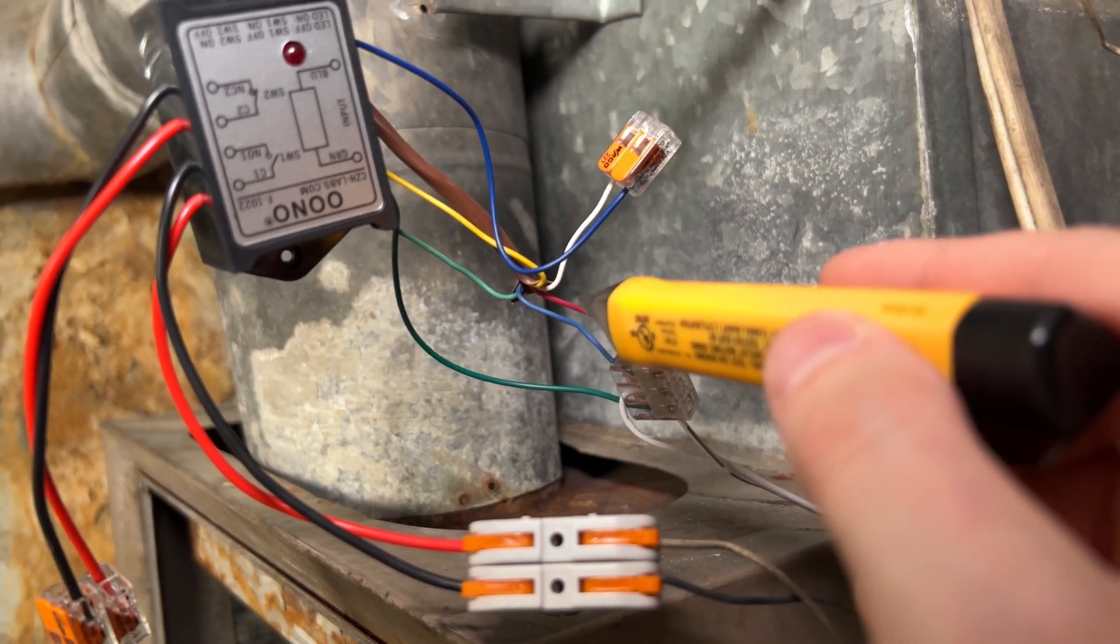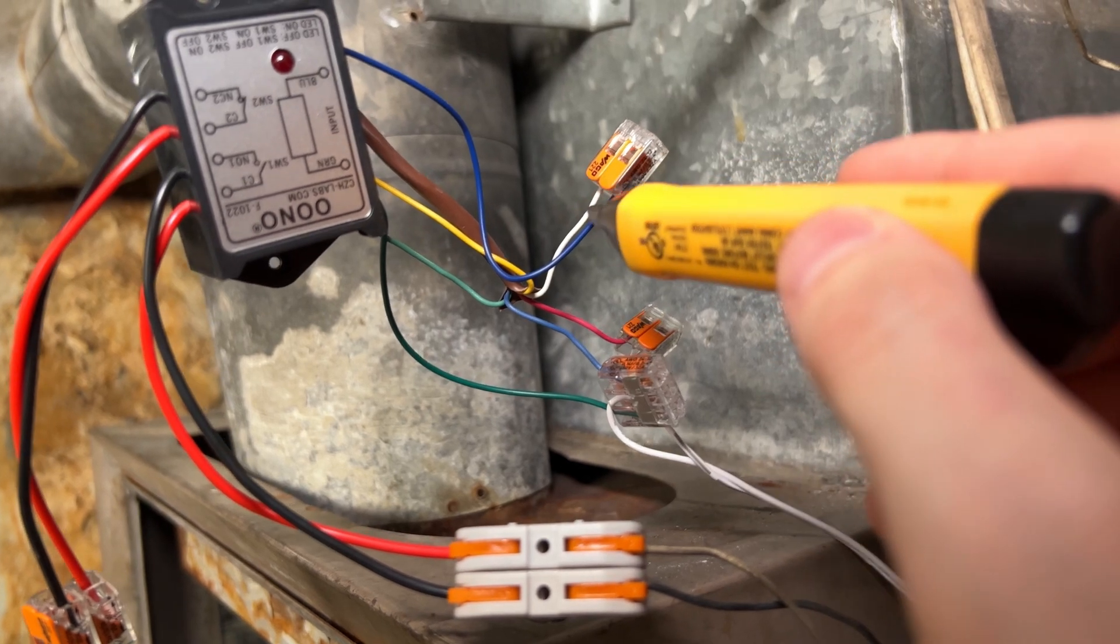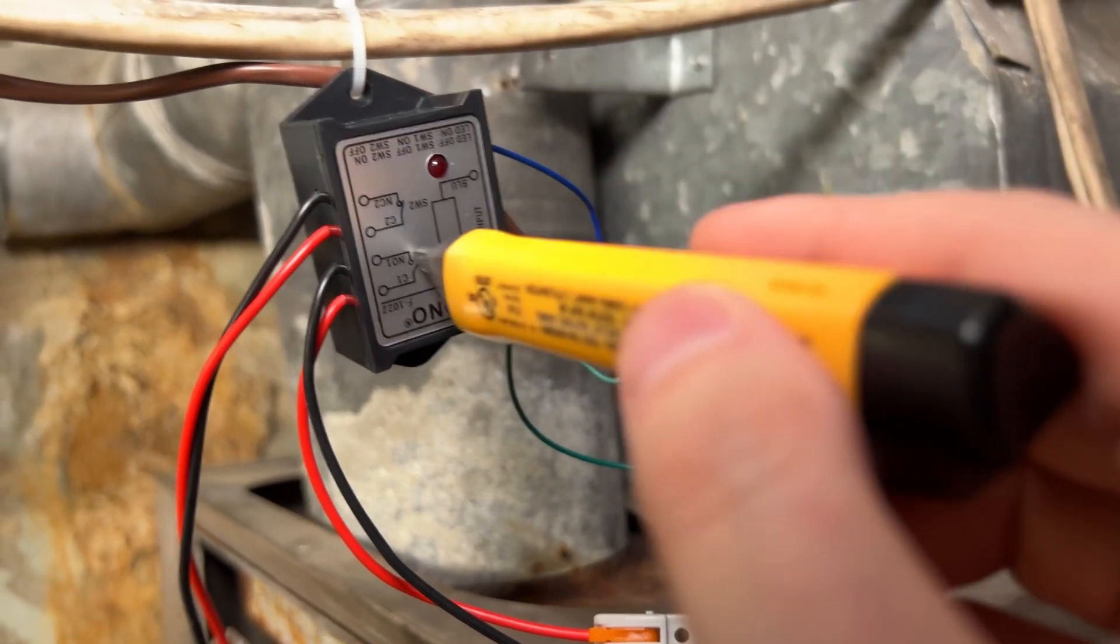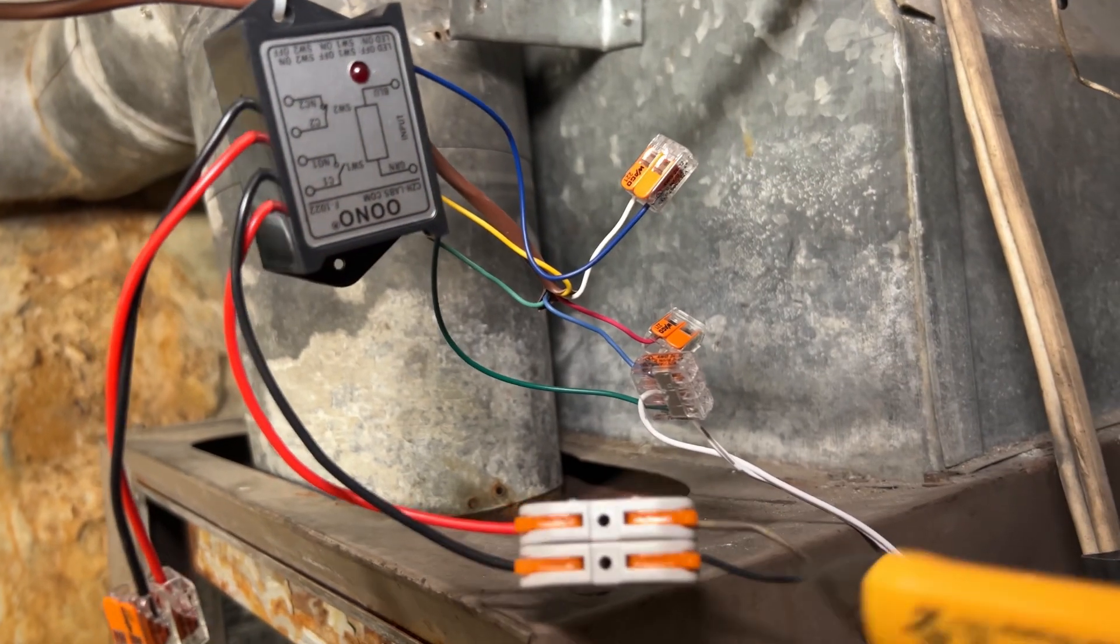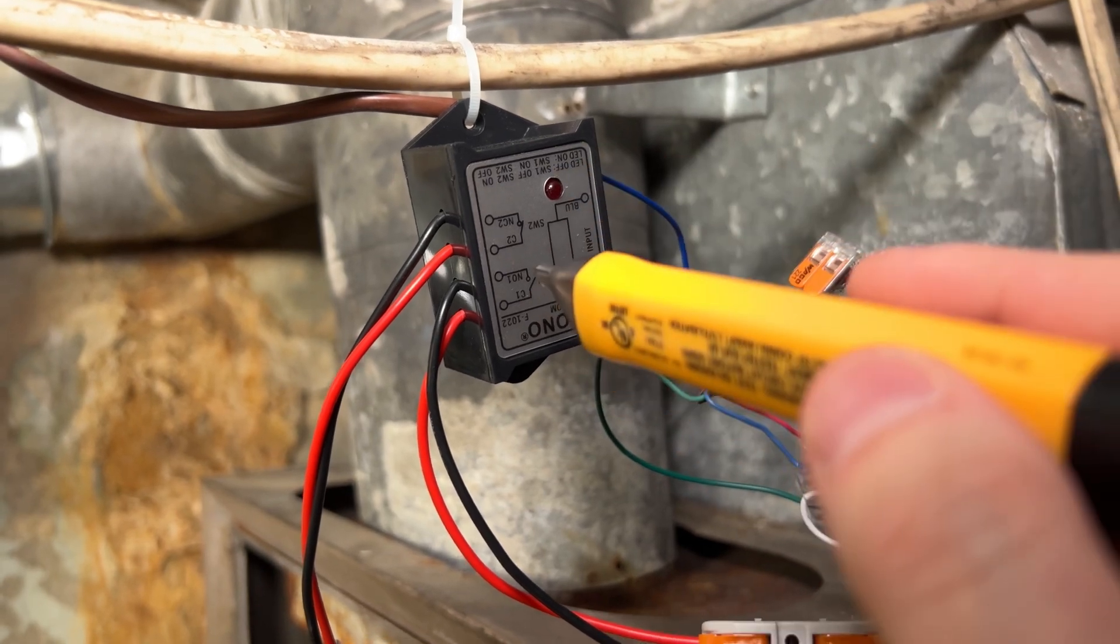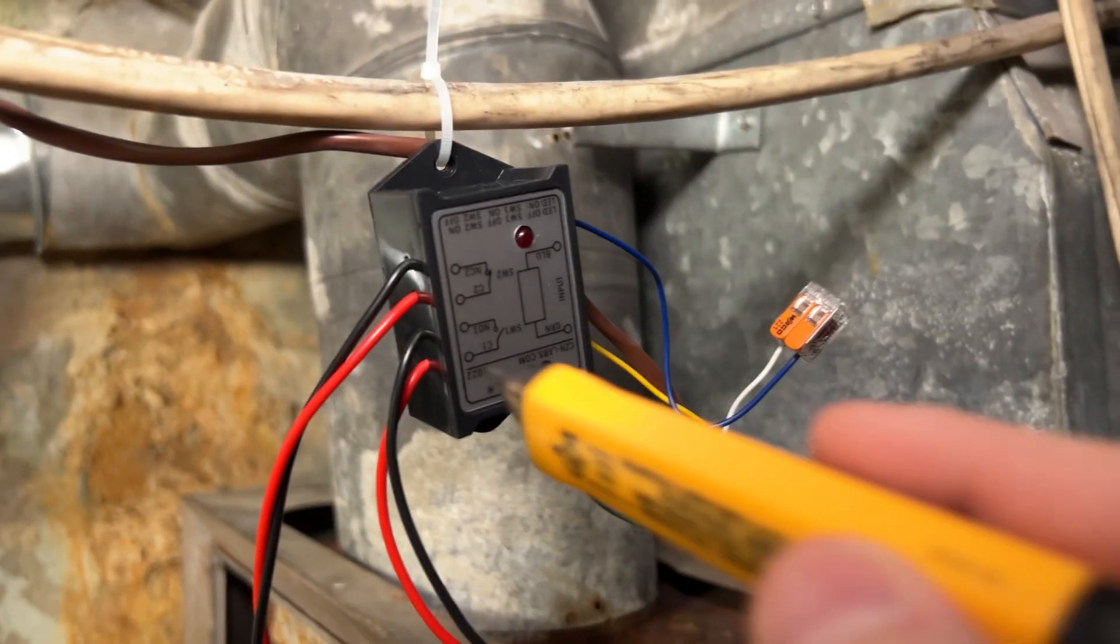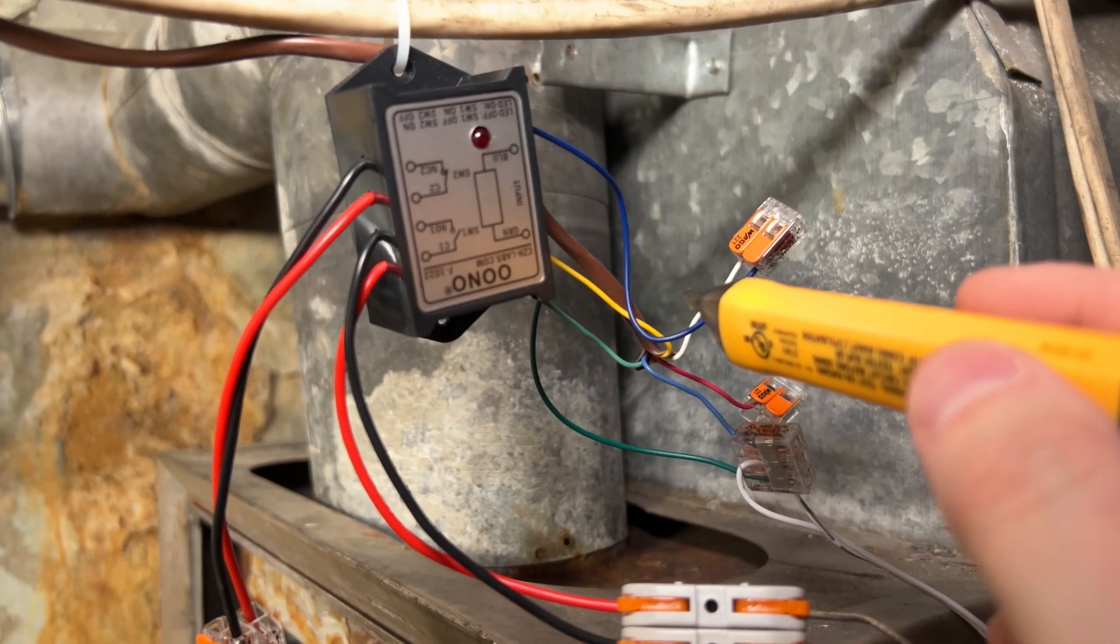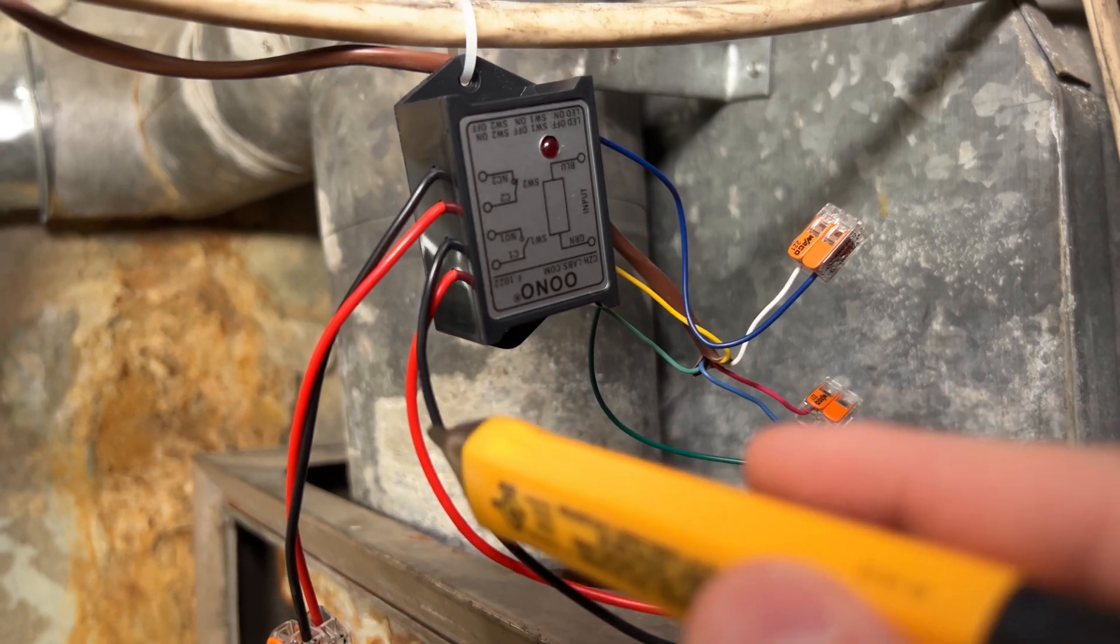Whenever the thermostat calls for heat it sends back 24 volts on this white wire, or W on the thermostat, and that goes to the other side of our relay. This is a relay. This allows us to take one circuit which is being powered by the external power supply and independently control another circuit, which is our black and white wires from our furnace, and the power does not cross over. So this power from our 24-volt power supply has nothing to do with this power from our furnace.